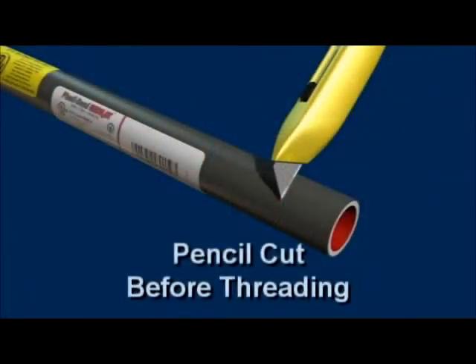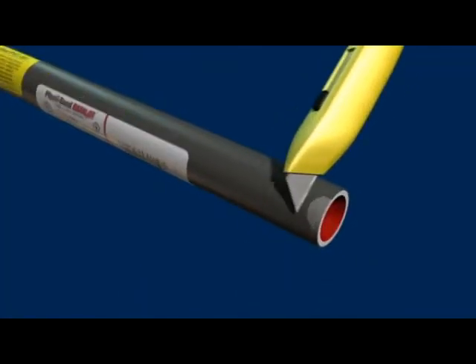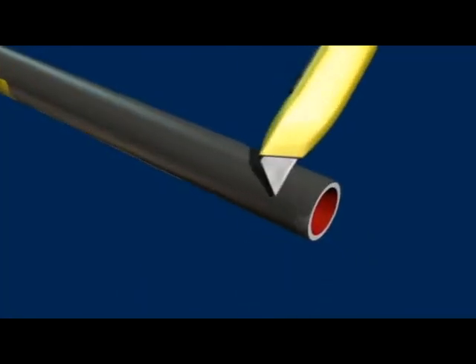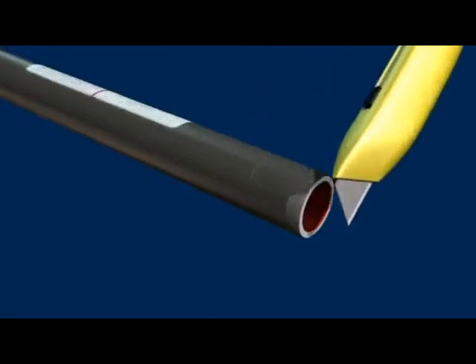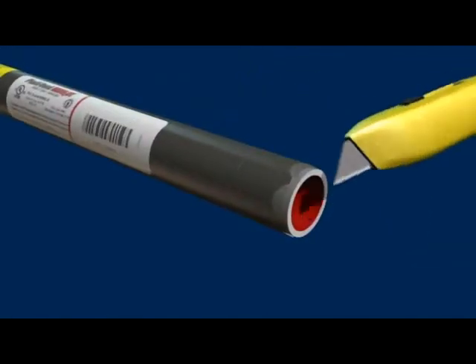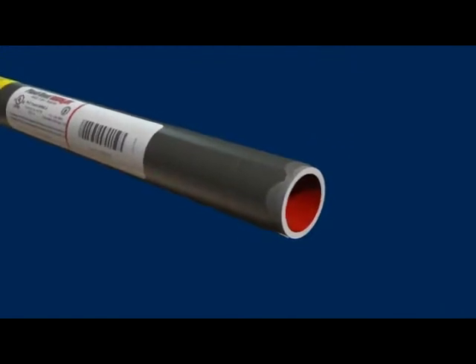Also, if conduit is to be threaded manually, it must be pencil cut before threading can occur. This will enable the die teeth on the threader to engage the conduit. In the same manner as sharpening a pencil with a knife, cut away one quarter inch of the exterior coating.